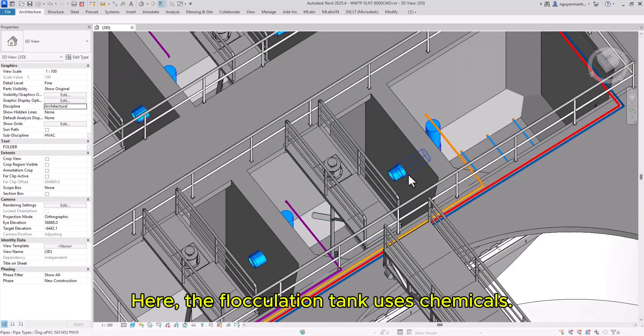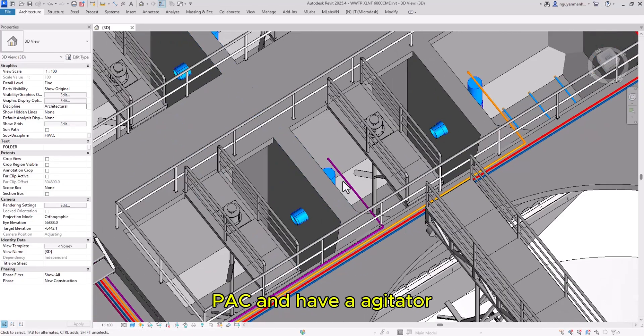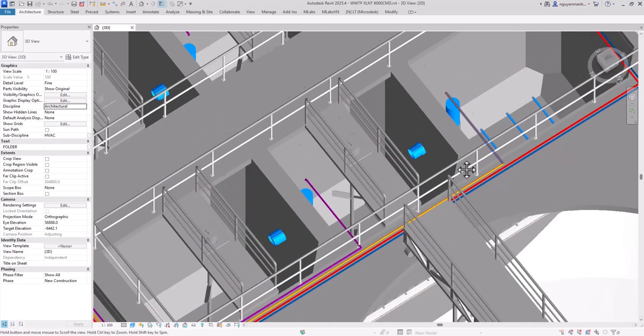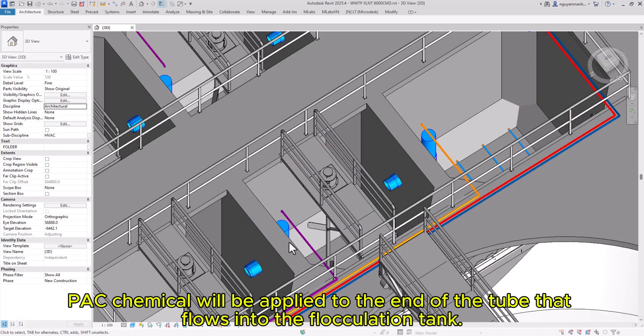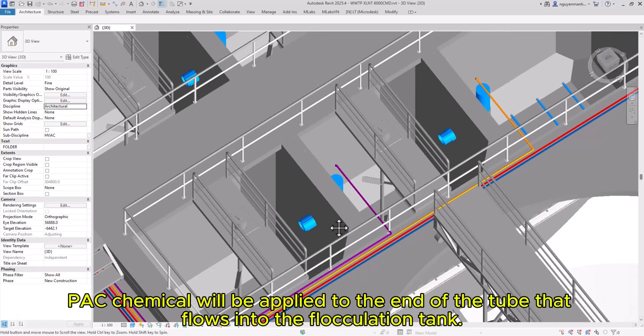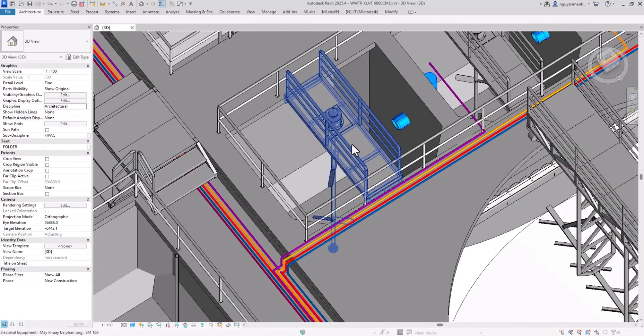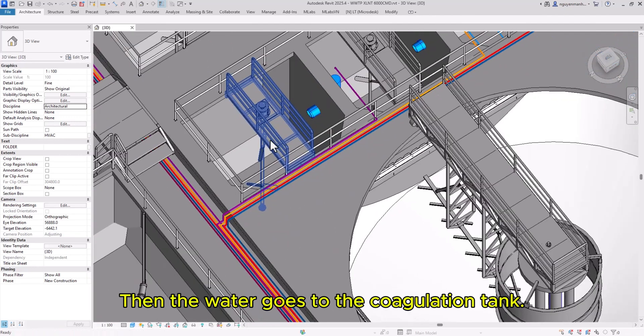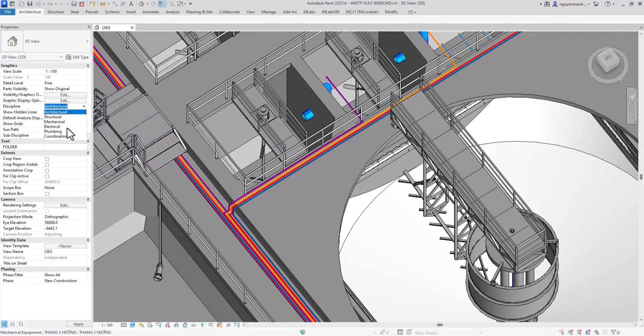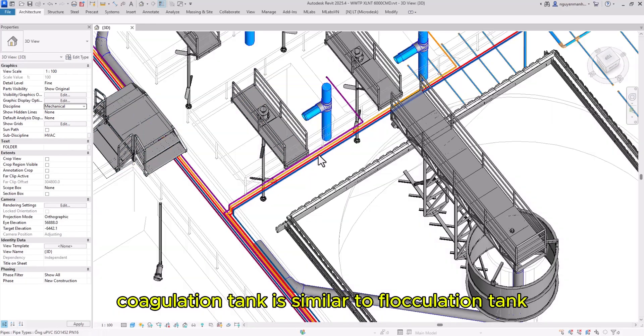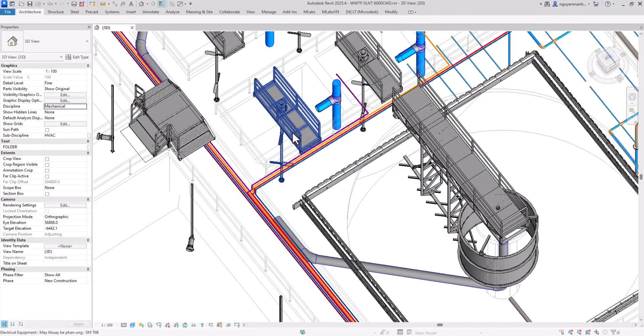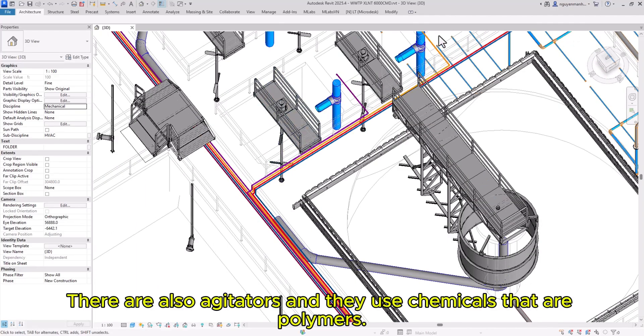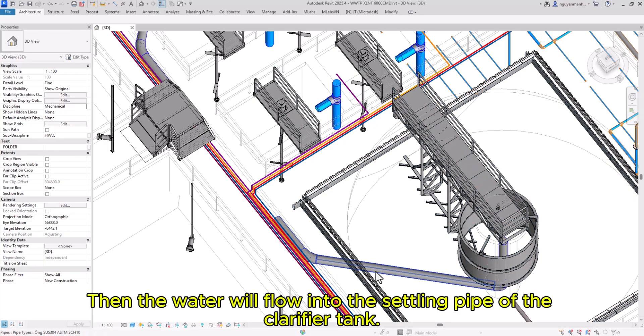The flocculation tank uses PAC chemical with an agitator. PAC is applied at the end of the tube flowing into the tank. Water then goes to the coagulation tank, which is similar to the flocculation tank. There are also agitators, and they use chemicals that are polymers.